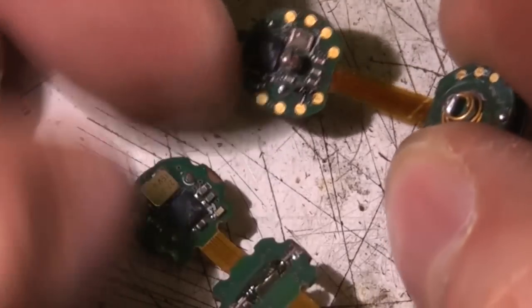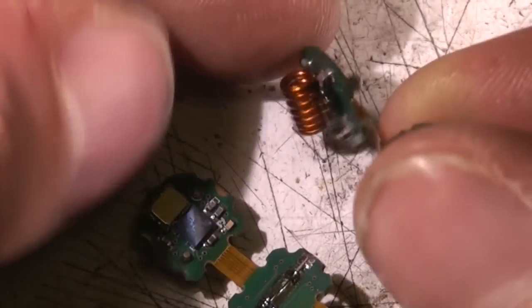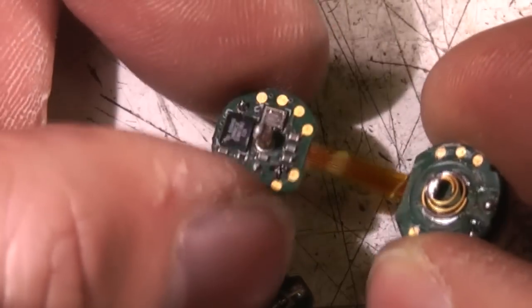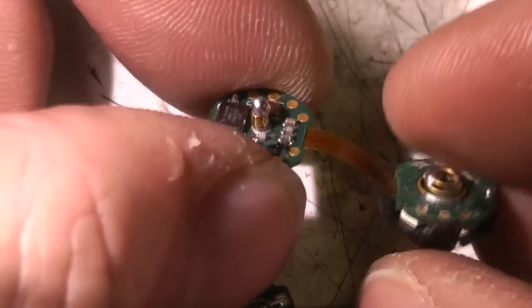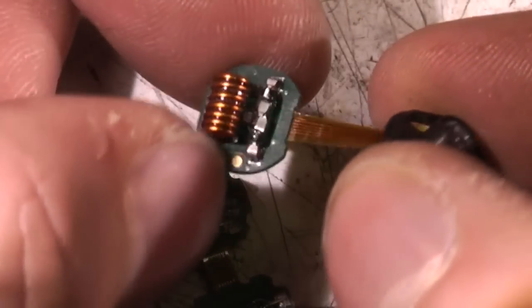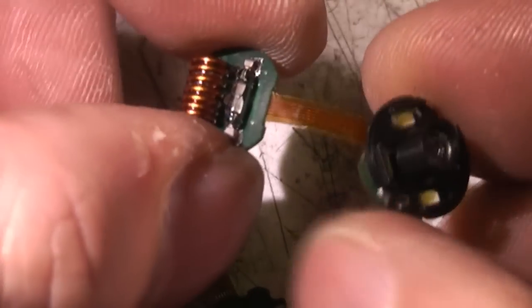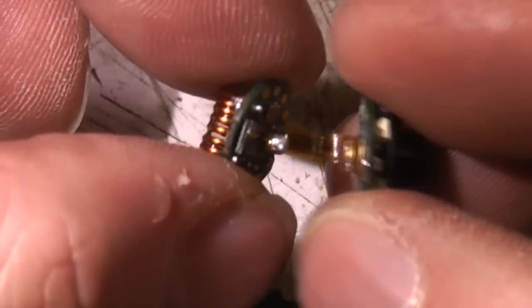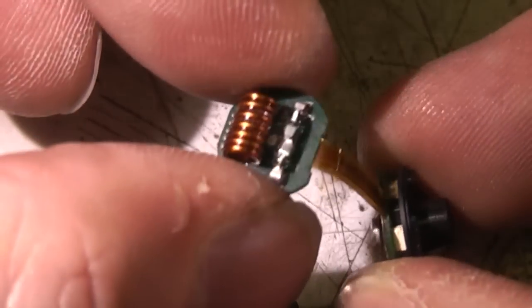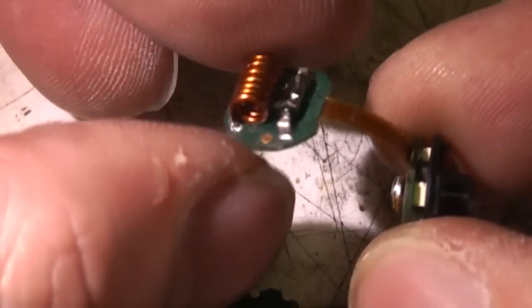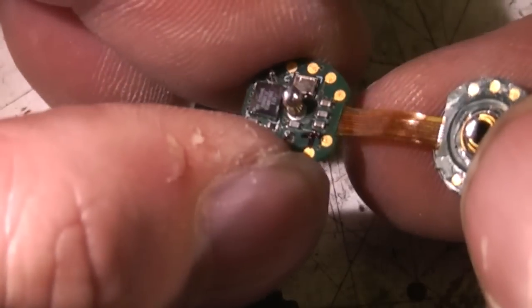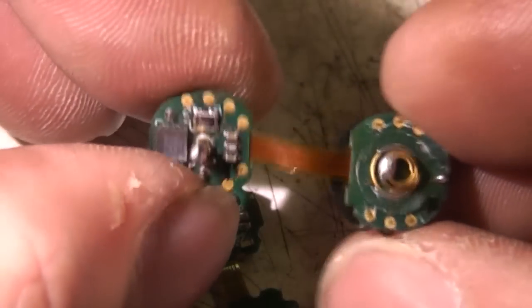So there you have it. Some more interesting medical pill camera tech. Not quite as highly integrated as the mirror cam. But then again integrating a 400 MHz transmitter on a camera chip is probably asking a little bit much and not really necessary. I mean this thing's down to two compact boards. There's just really the reed switch, the antenna, very few passives and really not much else.